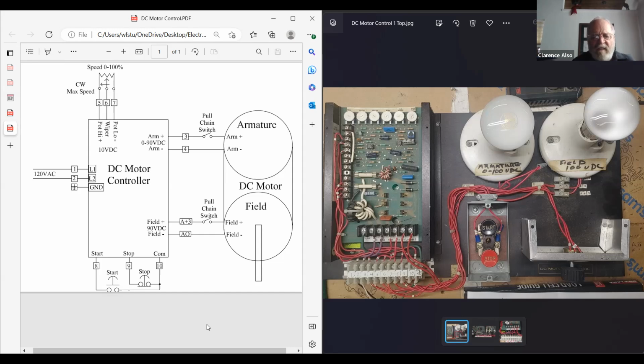So what does this DC motor require anyhow? Well, it's got two different windings on it. One is called an armature winding, another is called a field winding. And the field winding, you'll see it says field plus to field minus. That's 90 volts DC that comes out of the DC motor control to your field, and it's there all the time.